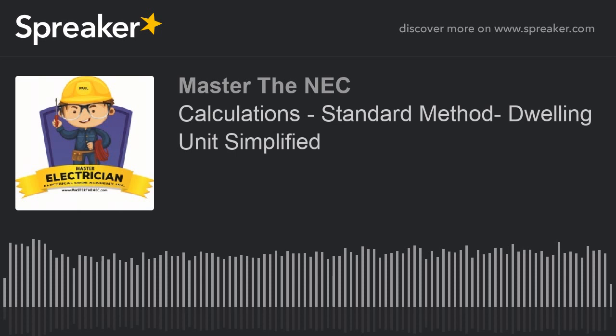So if we go look at Table 220.55, we're going to notice that our range falls under column C, and of course the table's heading reminds us that you're going to use column C in all cases except where permitted in Note 3.